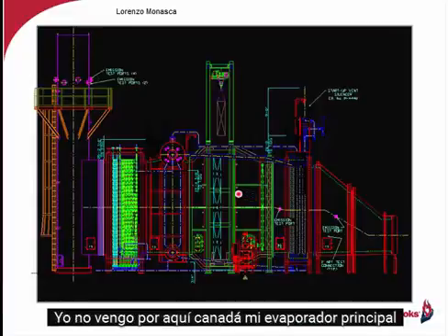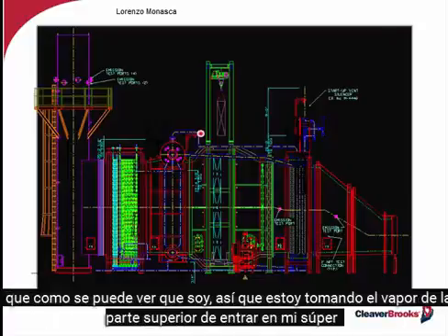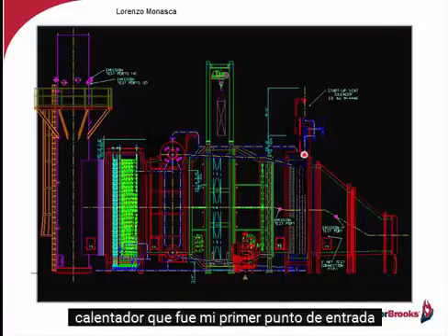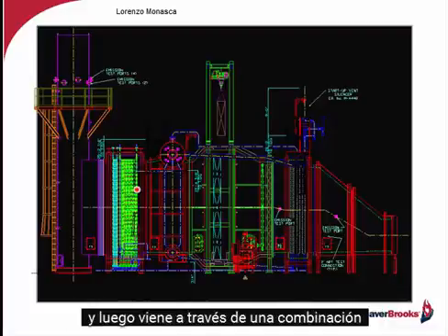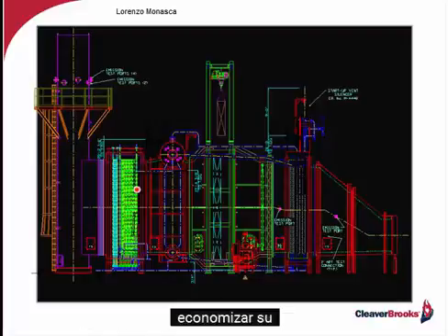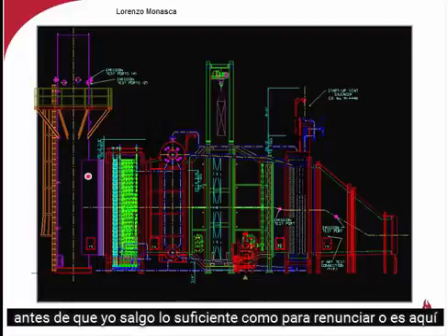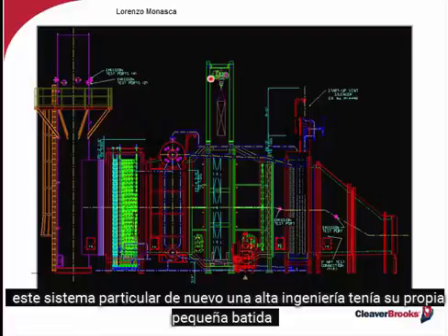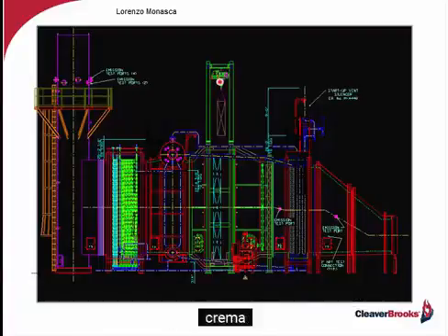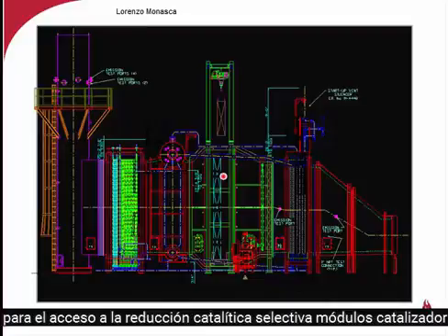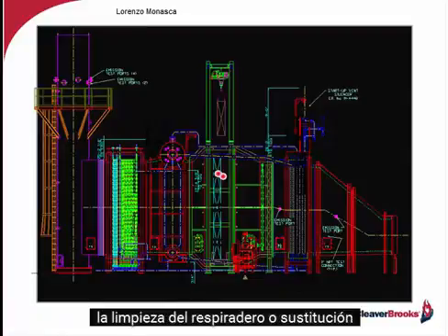I then come into my main evaporator, which, as you can see, I'm taking steam off the top going into my superheater, which was my first point of entry. And then coming through a combination economizer and condensate heater before I exit up and out the stack. Now notice right here, this particular system, again highly engineered, has its own little lift crane for taking out the selective catalytic reduction modules, the catalysts, for either cleaning or replacement.